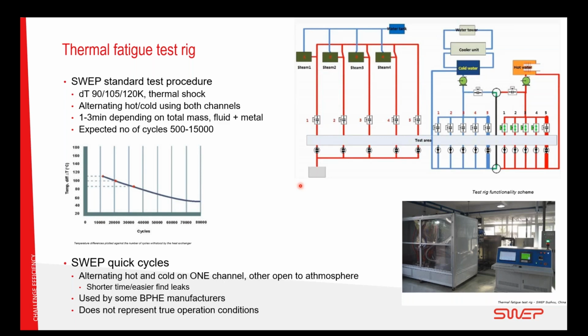So what we have created is this SWEP standard test procedure, where, taking us from the chart on the previous slide, we have the temperature differences of 90, 105, 120 K. And then we are alternating the hot and cold, and we are using both channels in the heat exchanger. So the one fluid is standing still, while the other, the hot one, is being pumped. This is done for 1 to 3 minutes depending on the total metal mass, and also the volume of the fluid on the other side. So everything is being heated up, and then we close the hot loop, and then we shock it thermally by opening the cold water into the heat exchanger to get the thermal shock here.